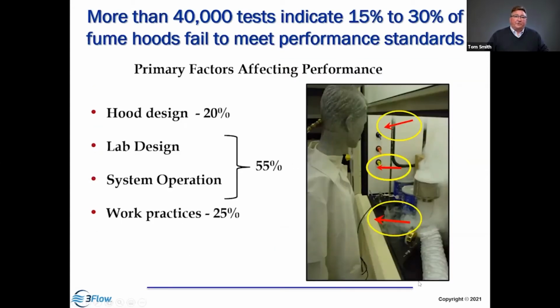Now, at 3Flow, we've done tens of thousands of tests, and this is a result from about 40,000 tests on hoods throughout North America, and we see about a 15 to 30% failure rate of laboratory hoods. And that means that 1 out of 5 to 1 out of 3 hoods is not functioning appropriately or optimized to protect the occupants. And when we look at the factors that influence that performance, 20% of the time it's due to the design of the hood, improper aerodynamics. But 55% of the time it's associated with the operation of the ventilation system or the design of the laboratory. So these factors are really critical. We have to be able to identify them and remove them in order for the hood to work.